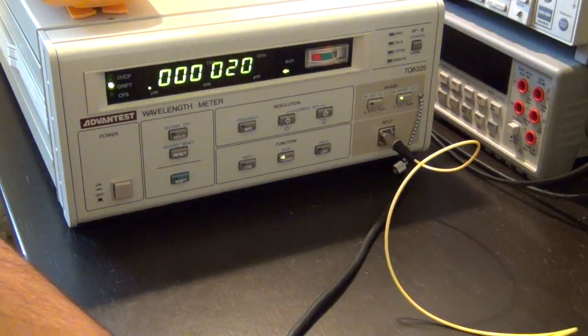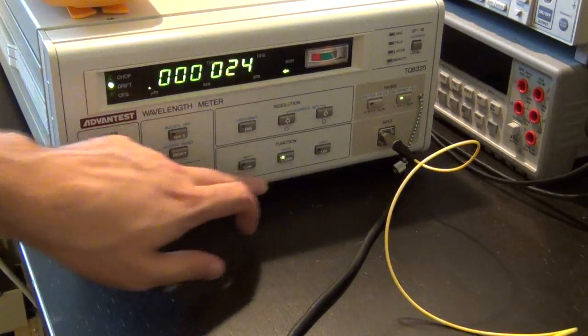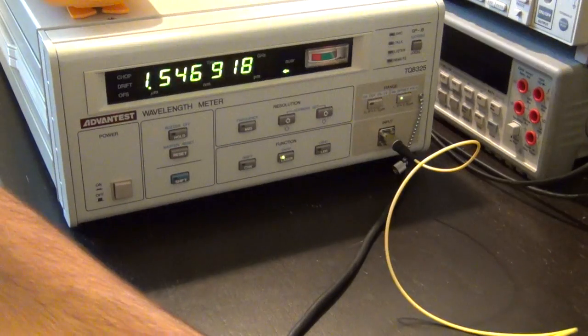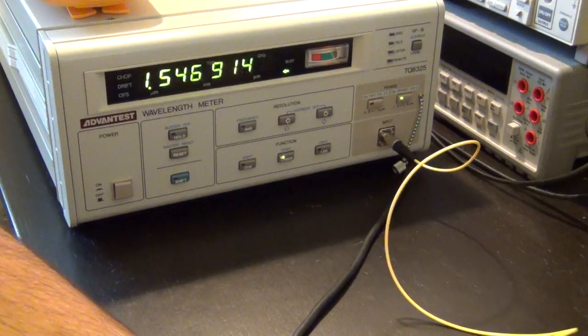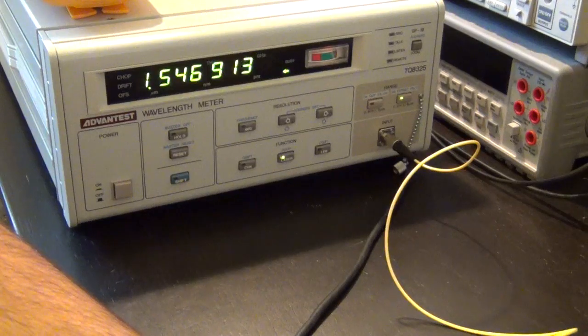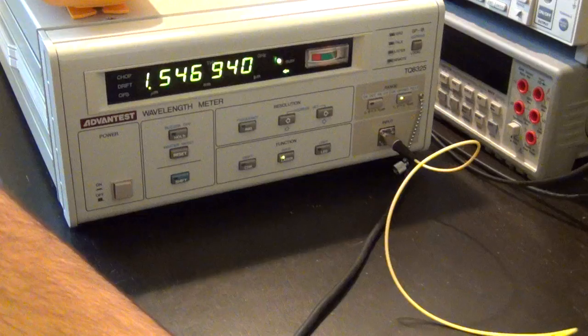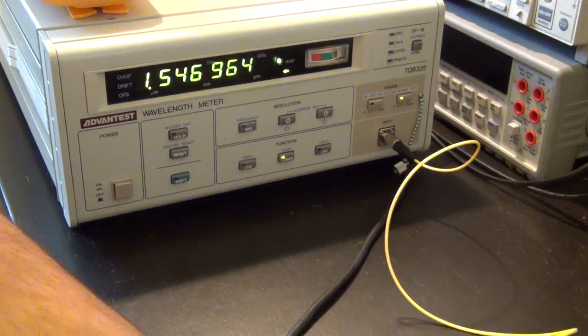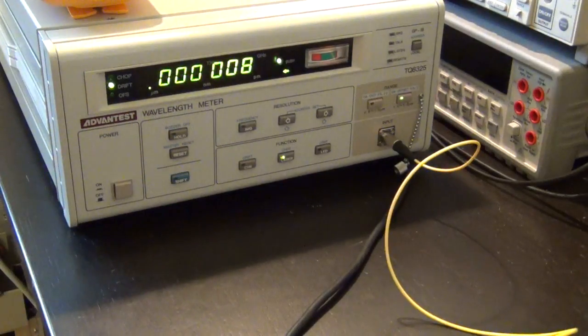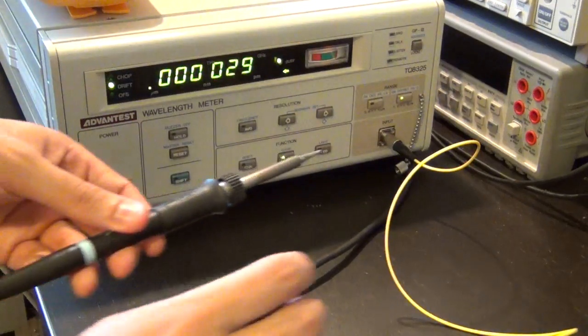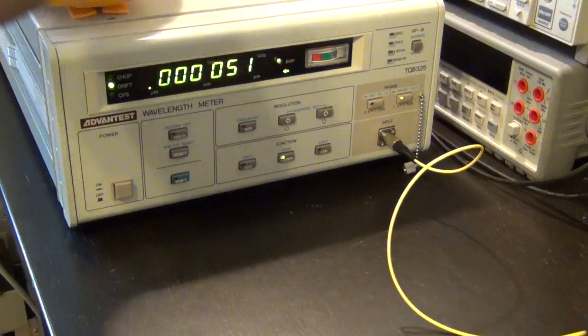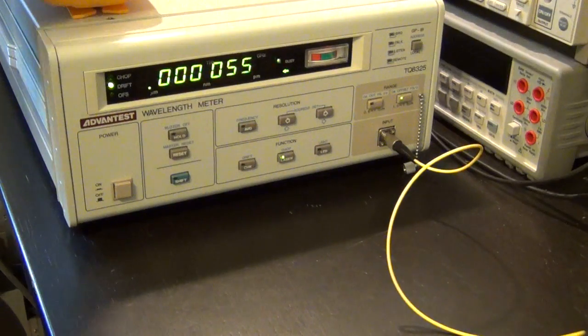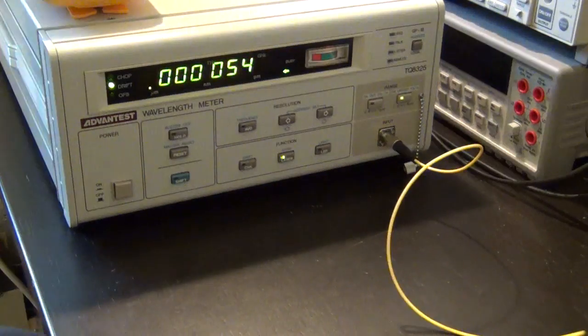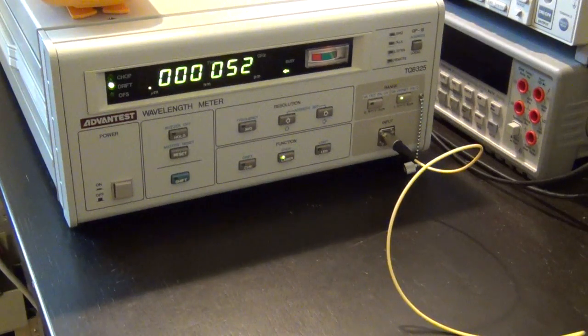It reset the drift. If I go back to measuring and turn the drift off, you can see the original wavelength again. Now I'm going to heat it up a little bit more, and then I'm going to remove the heat. You can see it's going to drift back to where it used to be. I'm going to heat it up a little bit more. There we go. It's not sufficiently warm, so I'm going to turn the drift back on. Now it's cooling back, reaching back to ambient temperature. So I put this back, and you can see that the wavelength is going to shift back to where it used to be. There it is. It's slowly going back in the right direction.